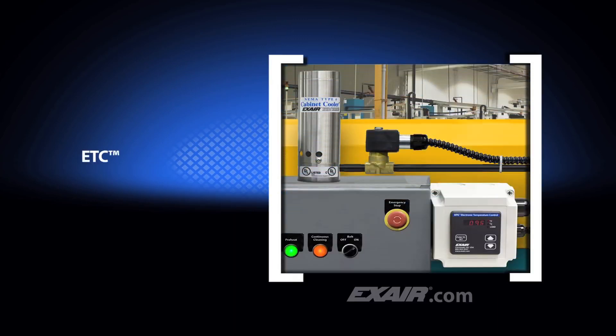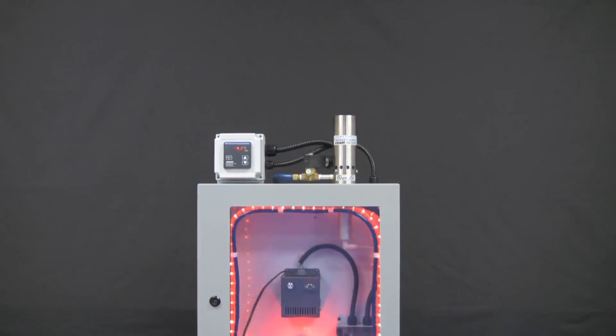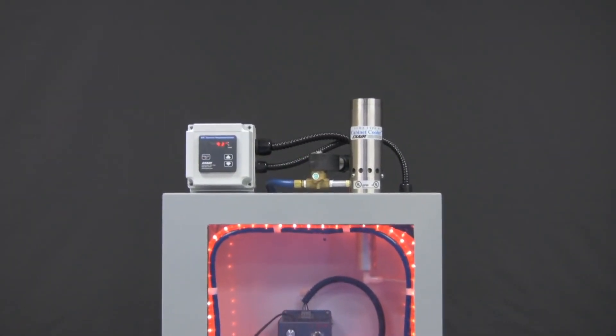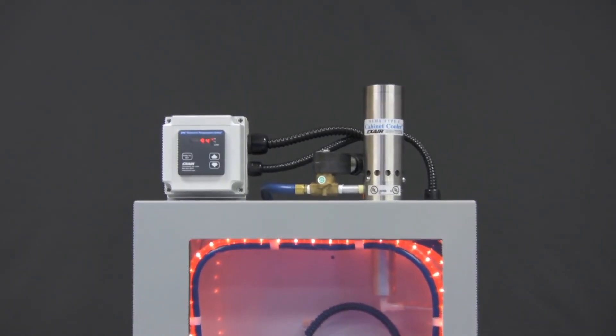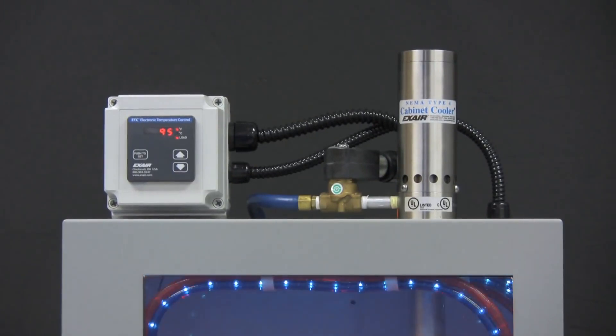If you prefer digital temperature control, EXAIR has the ETC, Electronic Temperature Control. This controller can accurately maintain a constant temperature slightly under the maximum rating of the electronics, permitting just enough cooling without wasting compressed air. The temperature inside the enclosure is constantly monitored by a quick response thermocouple, with an LED display on the ETC showing either degrees Fahrenheit or degrees C. The control activates the included solenoid valve when the temperature setting has been exceeded. The ETC is also CE compliant to assure safe operation.